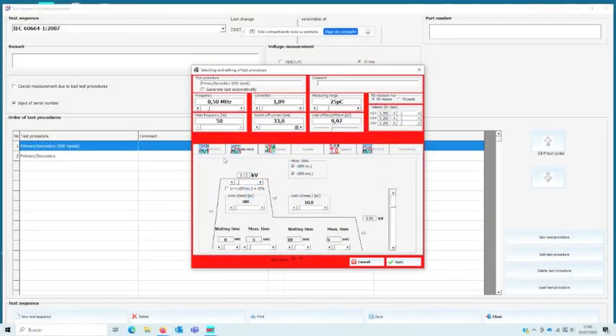So this is the software that we use together with the partial discharge equipment to make the test. This software allows us to make the test according to the different standards. Now we will use this test procedure for the 60664 standard. This standard consists of increasing the voltage up to 1.875 times the working voltage, then decreasing it to 1.5 times the working voltage, and then in the last 5 seconds making the measurements. So the test is considered successful if there are no partial discharges in the last 5 seconds of the measurements.